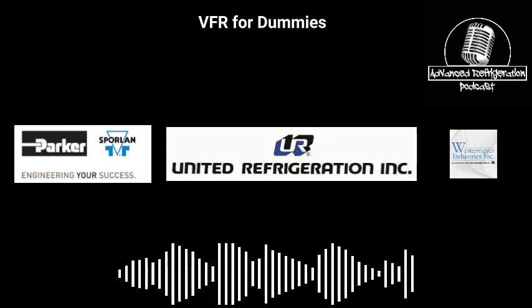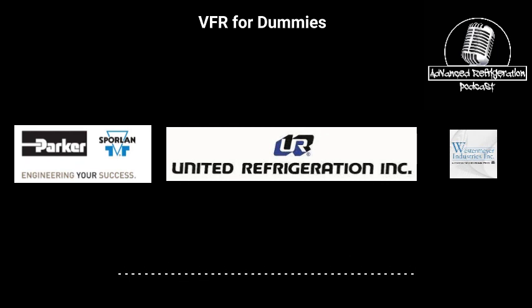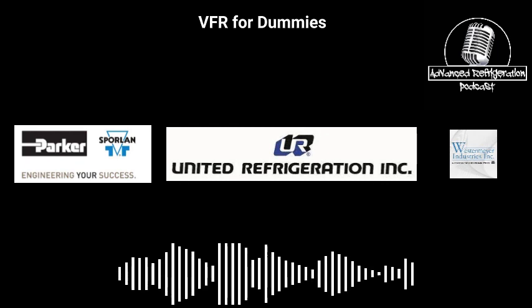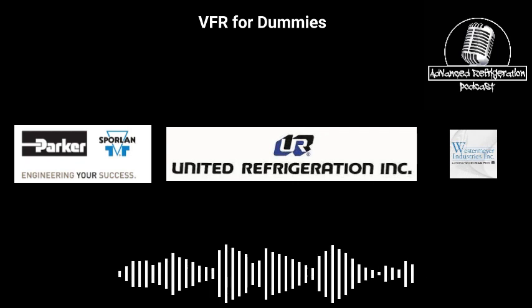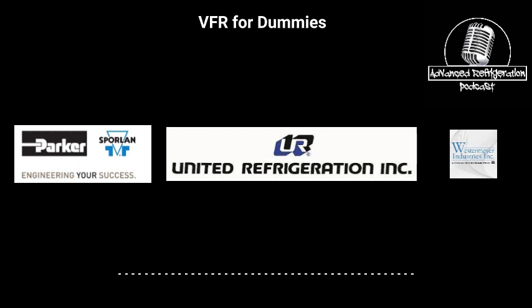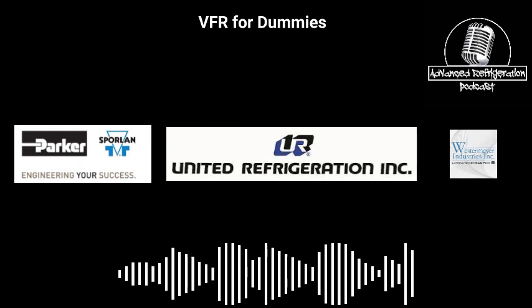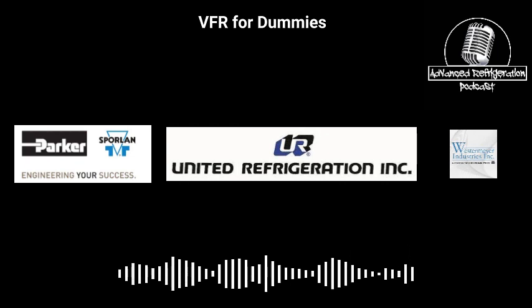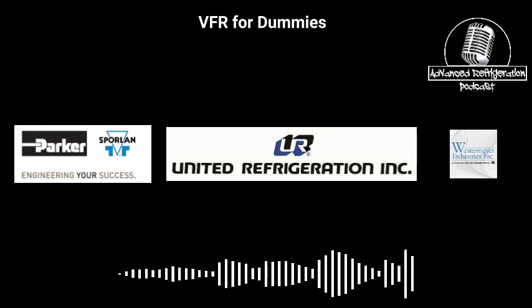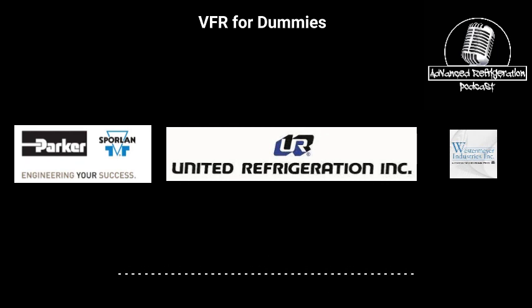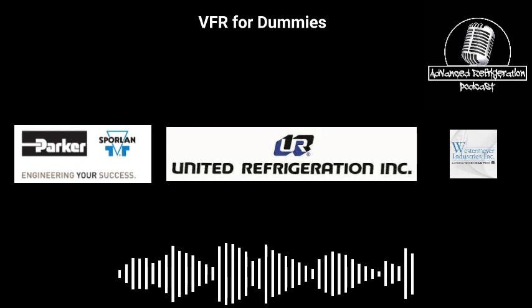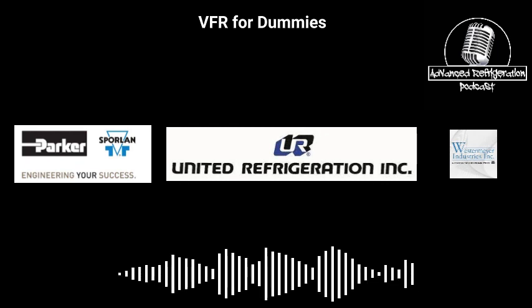The compressor is going to do what it can to maintain the call indoors. 50% load is probably going to push into cooling control, and then the heating units are going to suffer a little bit, but not crazy. So I'm going to share the basic operation. Okay. So normal cooling, we're doing PI control, high pressure control or low pressure. Zoom in just a little bit more, Don. So yeah, outdoor fans will ramp up and down when it's in cooling mode? The fans will change speed in either mode. They're inverter driven fans.